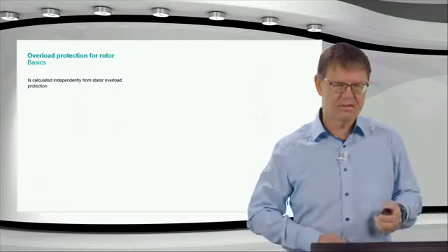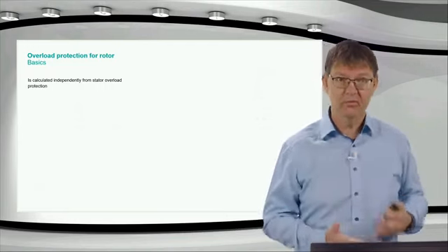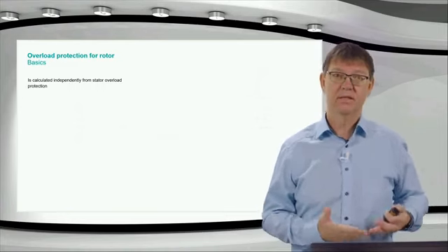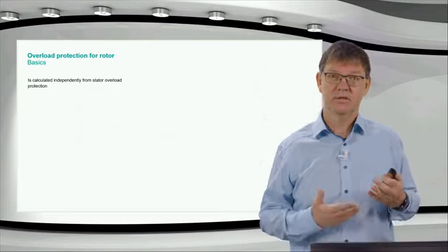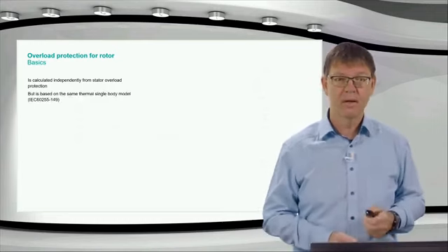Okay, let's go directly into maybe a little bit difficult topic. I will give this just as a rough overview. How do we make the overload protection for the rotor? It's calculated independently from the stator overload protection. So we have two separate functions.